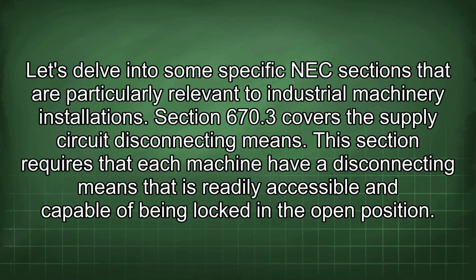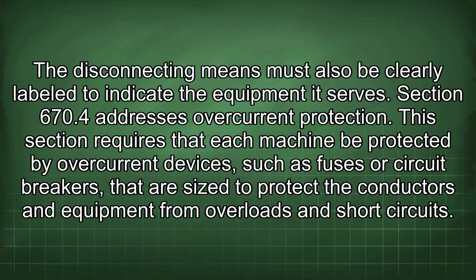Let's delve into some specific NEC sections that are particularly relevant to industrial machinery installations. Section 670.3 covers the supply circuit disconnecting means. This section requires that each machine have a disconnecting means that is readily accessible and capable of being locked in the open position. The disconnecting means must also be clearly labeled to indicate the equipment it serves.